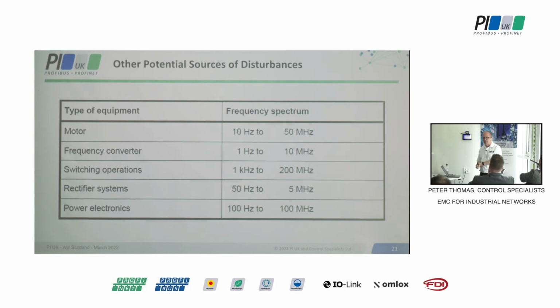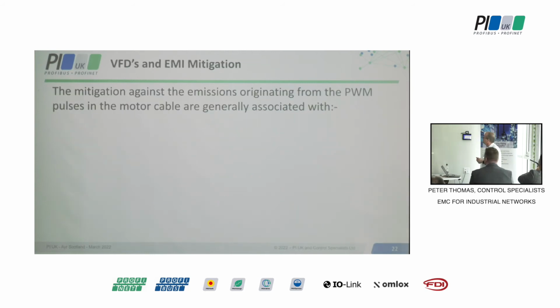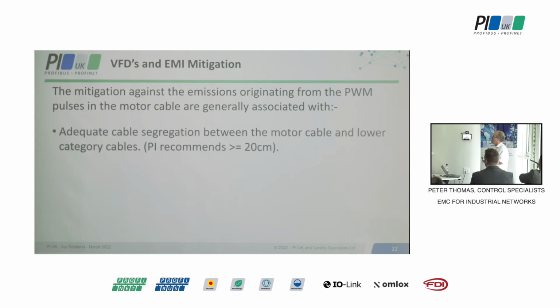One of the things that I'll be talking about shortly is something called the frequency of concern. Whenever we've got EMC issues and we're trying to improve the system, we need to know what the frequency of concern is, because that's going to tell us how much we've got to spend to improve things. The mitigation against the emissions from this pulse width modulation is generally associated with adequate cable segregation between the cable and any sensitive cable. So we're basically saying at least 20 centimeters.